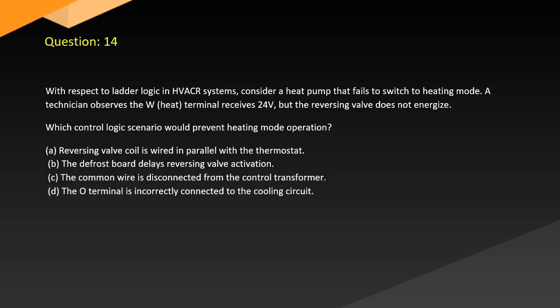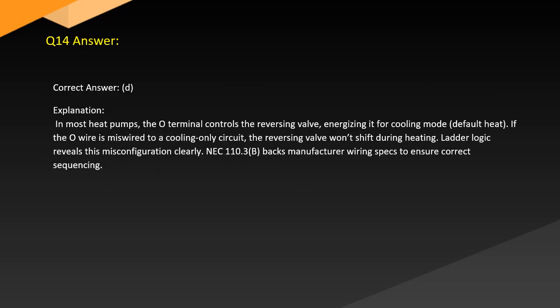C. The common wire is disconnected from the control transformer. D. The O terminal is incorrectly connected to the cooling circuit. Answer. Correct answer: D. Explanation. In most heat pumps, the O terminal controls the reversing valve, energizing it for cooling mode, default heat. If the O wire is miswired to a cooling-only circuit, the reversing valve won't shift during heating.